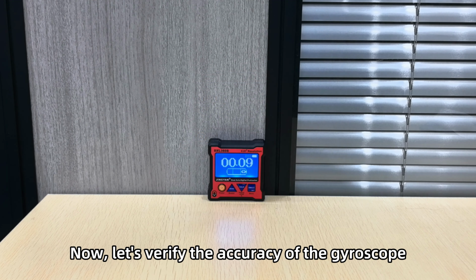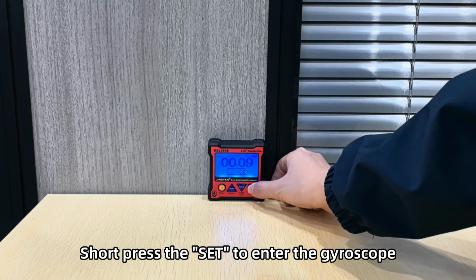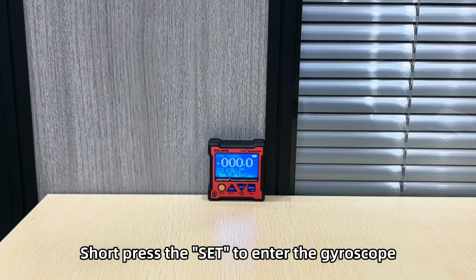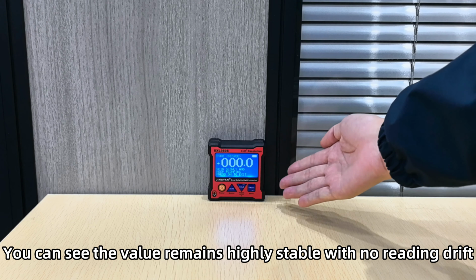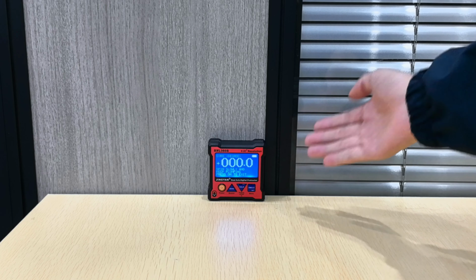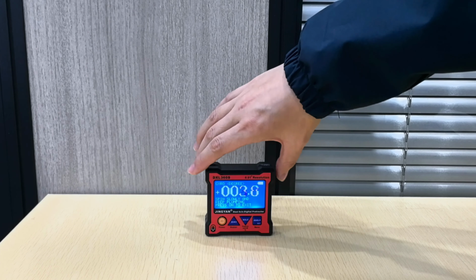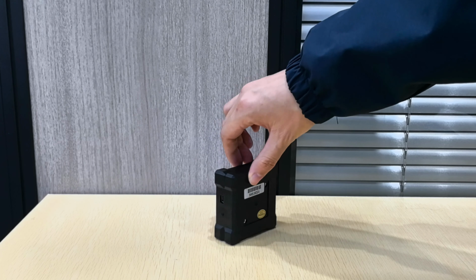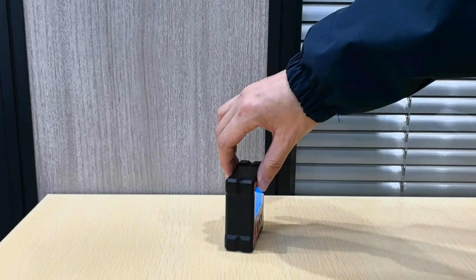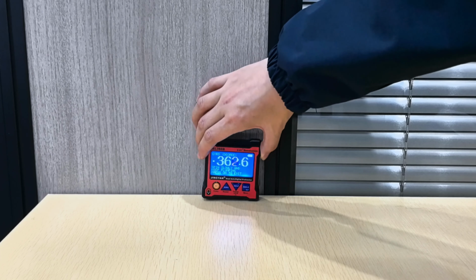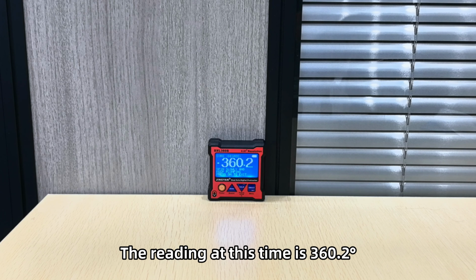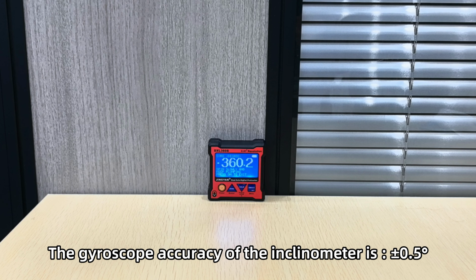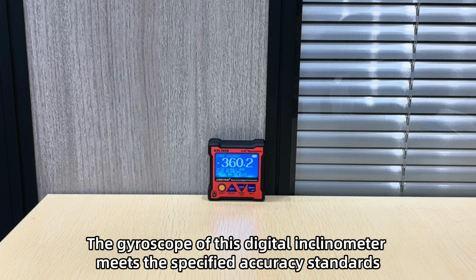Now, let's verify the accuracy of the gyroscope. Short press the set to enter the gyroscope. You can see the value remains highly stable with no reading drift. The reading at this time is 360.2 degrees. The gyroscope accuracy of the inclinometer is ±0.5 degrees. The gyroscope of this digital inclinometer meets the specified accuracy standards.